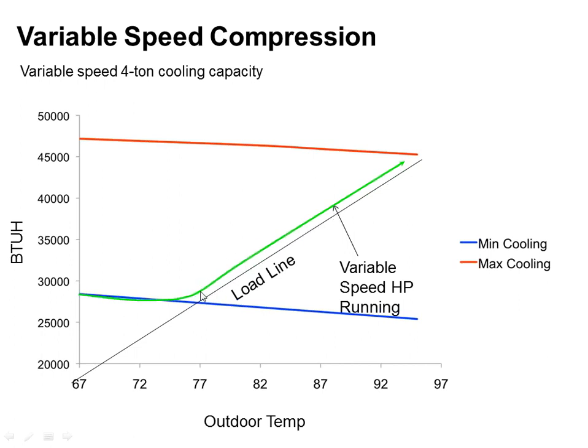It's going to try to take this green line and match its capacity to what your house needs at that moment. Now, at some point, it's going to get so mild outside that it's going to ramp down to minimum, for example, 40% on a 3-ton unit, and it can't ramp down any farther. When we get to that point, the only thing it can do is actually shut off. So it ramps down to 40%, and it still gets milder and milder outside. It'll have to shut off. Then it'll cycle between 0 and 40% capacity, which is still better than going 0, 100% capacity, or 0, 80% capacity on a 2-stage unit. It'll go 0, 40, 0, 40.